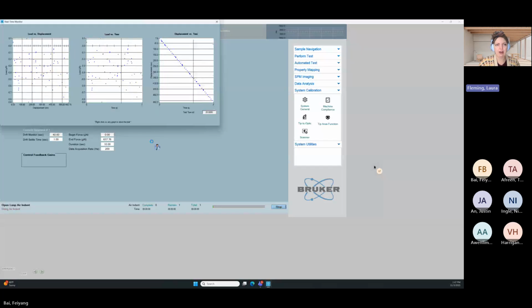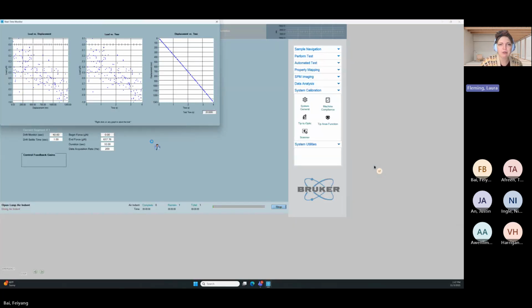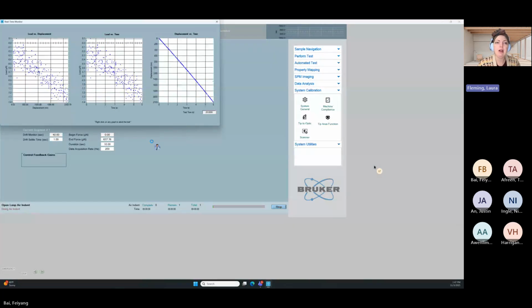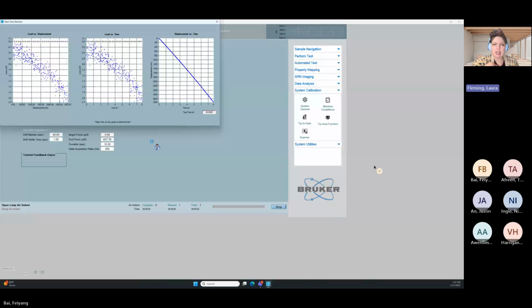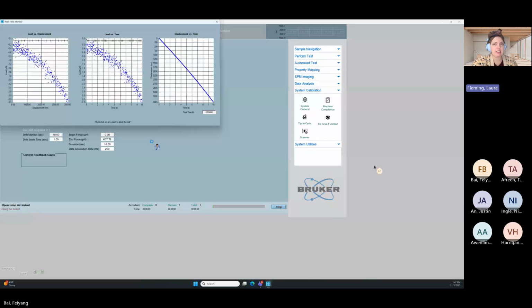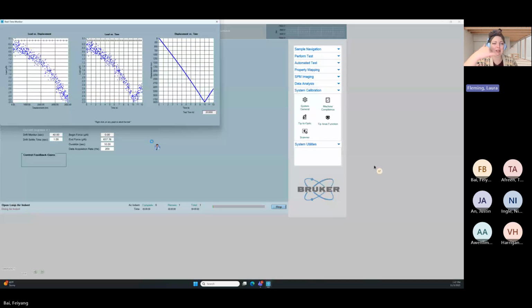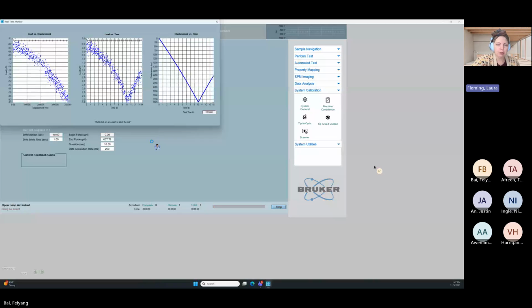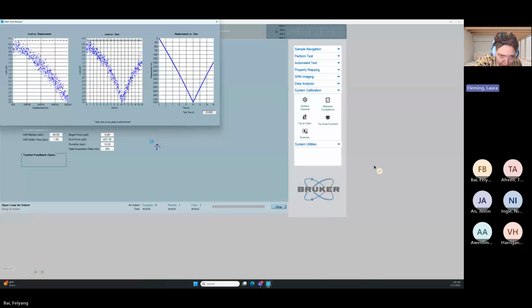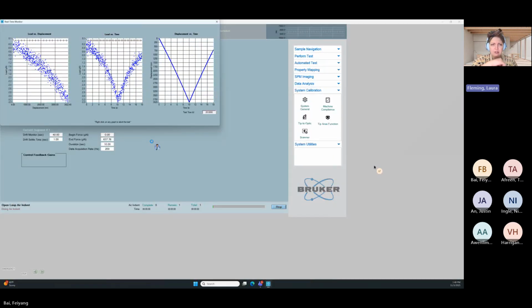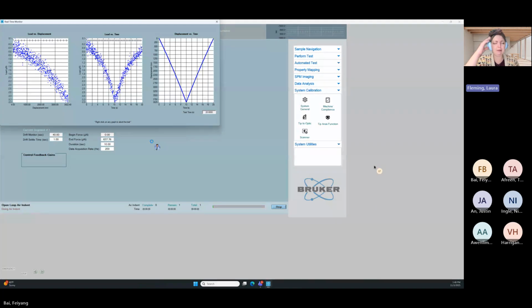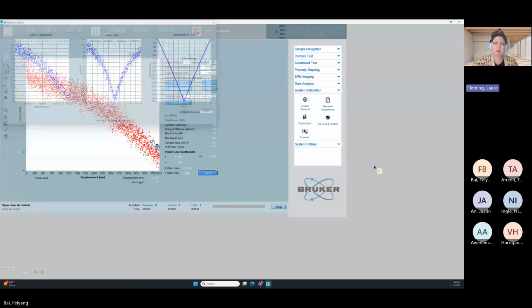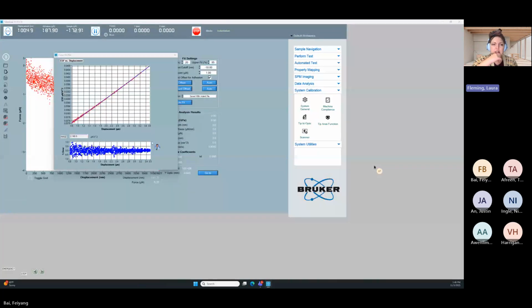And we get 3 live graphs here. We get load versus displacement, load versus time, and displacement versus time. I'm always looking at displacement versus time. Is the transducer moving? Because if it's not, that's your sign to call Laura. That means something's wrong, that we need to talk. So here we can see it actuated out to about 3925 nanometers, 3.9 microns, which is the majority of its range, which is what I expect it to cover.